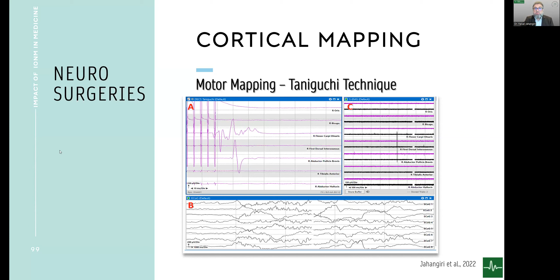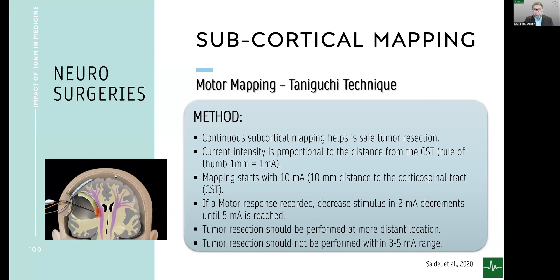This is patient data for motor potentials using low frequency, only a few pulses. It has very low after-discharges. For subcortical mapping, once you go into the white matter tract, we can stimulate with monopolar stimulation. The theory is that every 1 milliampere of current equals 1 millimeter. So we have to stop at 5 to 7. If you get a response at 5 or 7 milliamperes, you have to stop because you're less than 5 millimeters away. If you go further, the data shows the patient will end up with a deficit. That doesn't apply to cortical responses, only to subcortical.